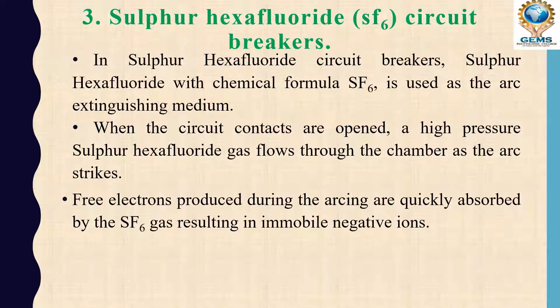Free electrons produced during the arcing are quickly absorbed by SF6 gas, resulting in immobile negative ions. The reason an arc forms is because of free electrons. Electrons carry current from one place to another. So if we remove these electrons, there is no chance for the arc to sustain.